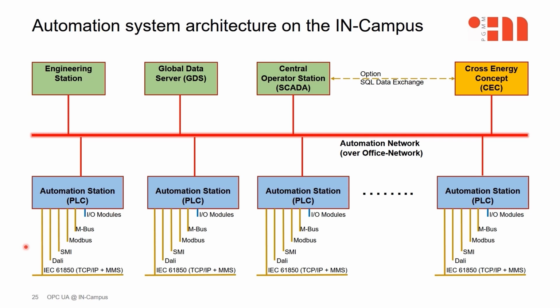Let's now take a look at the architecture of the automation system on the INCampus. You can see that the automation network is integrated into the office network as required. The automation stations communicate with the SCADA system, the global data server, the cross-energy concept, and the programming stations via this network. For their part, the automation stations have contact with all field devices and building systems, either via direct inputs and outputs or via defined field bus systems.